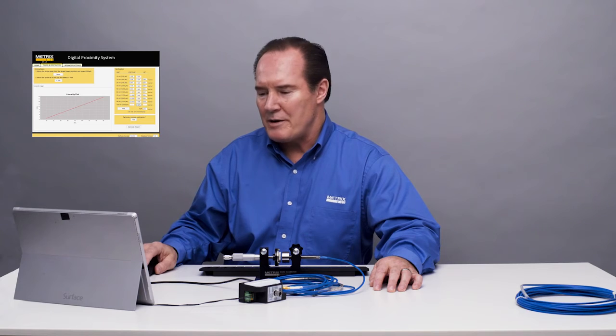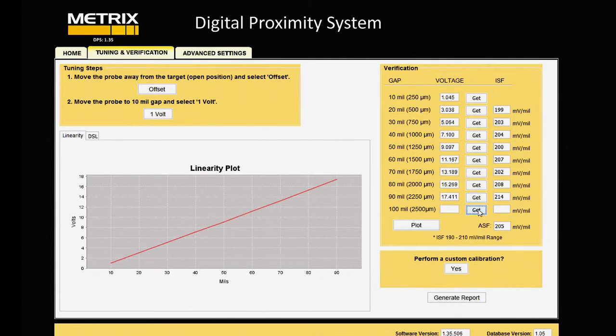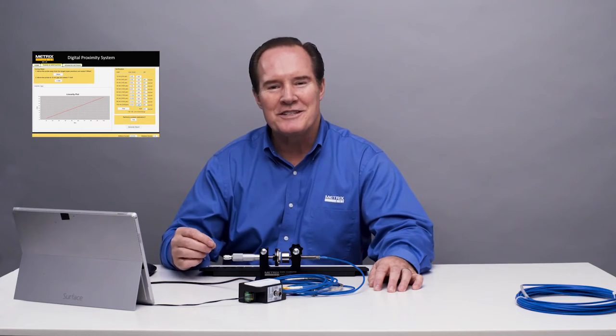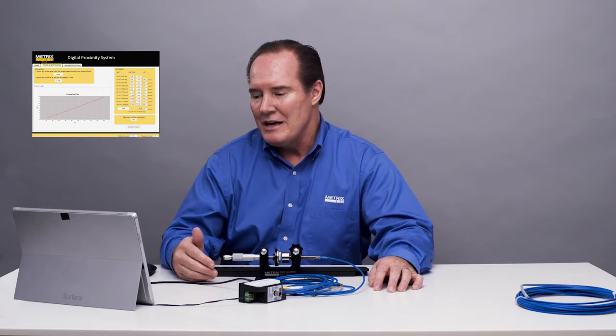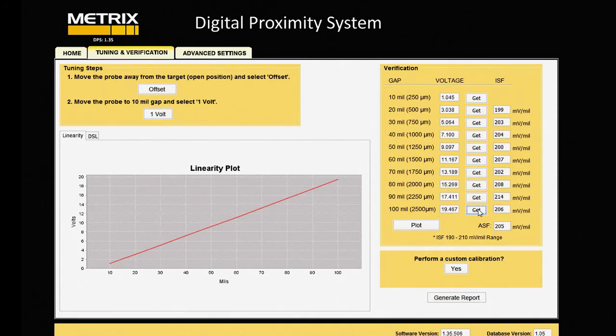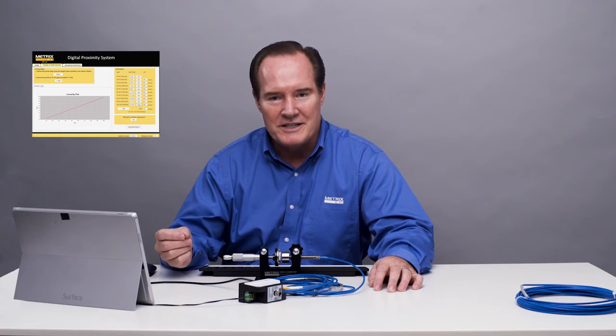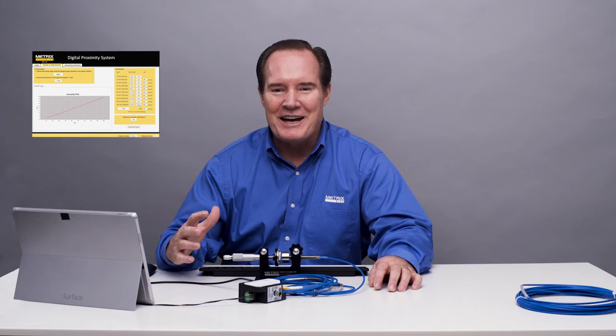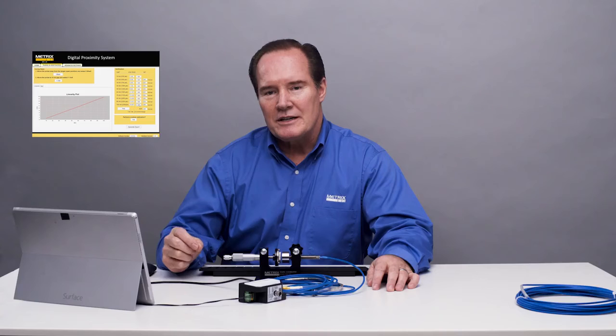All right, this is our last data point, and that's all the way out to 100 mils in this tight situation. It's doubtful you'll ever be out that far. But what's nice is that it works pretty well. You can see from the results that we'd like to be between 190 and 210. Now, the API doesn't actually address this situation: what are the specifications for this tight situation? Typically, you'd like to have no metal near the tip. But in this case, because of the machine's construction, we do have metal near it. So we get a nice linear characteristic.